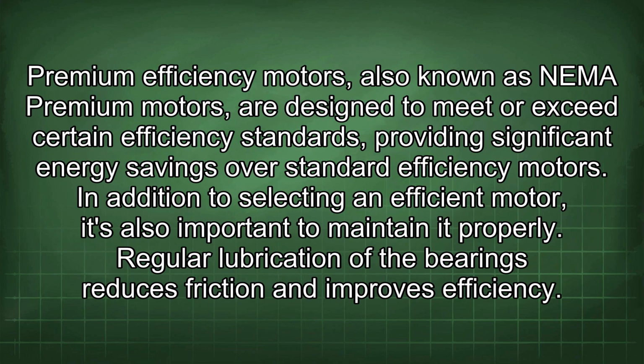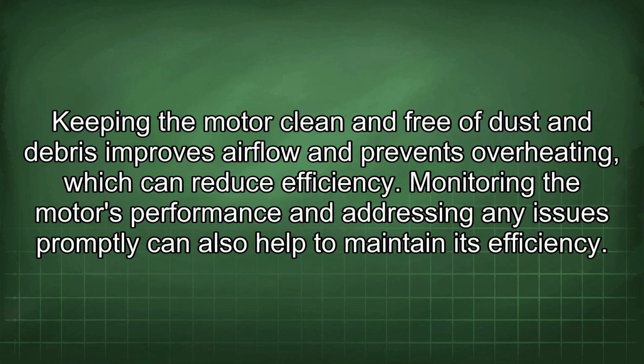Premium efficiency motors, also known as NEMA premium motors, are designed to meet or exceed certain efficiency standards, providing significant energy savings over standard efficiency motors. In addition to selecting an efficient motor, it's also important to maintain it properly. Regular lubrication of the bearings reduces friction and improves efficiency. Keeping the motor clean and free of dust and debris improves airflow and prevents overheating, which can reduce efficiency. Monitoring the motor's performance and addressing any issues promptly can also help to maintain its efficiency.